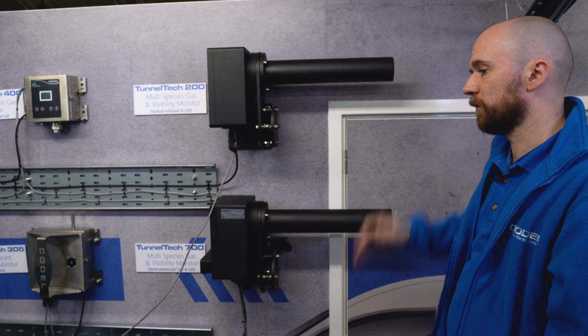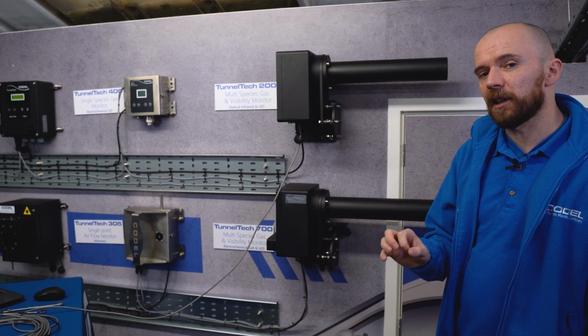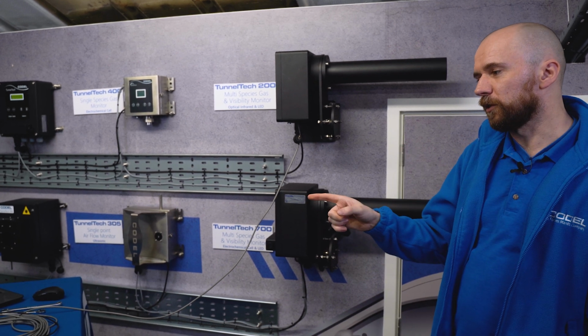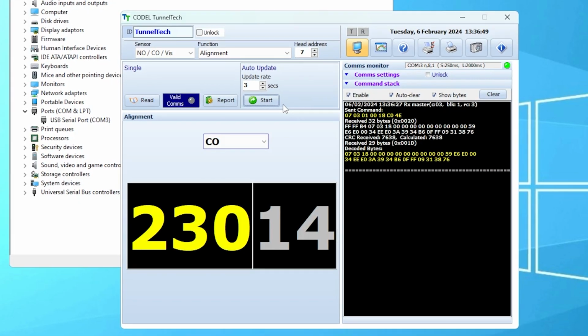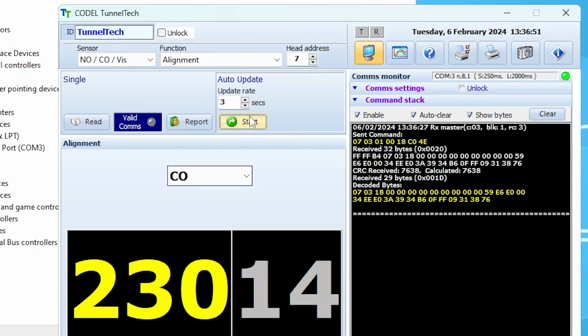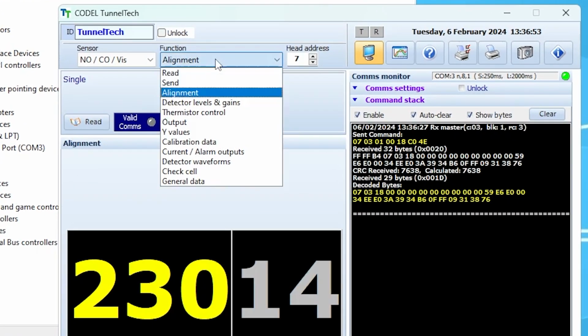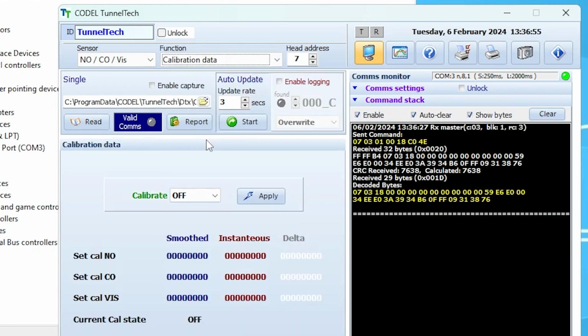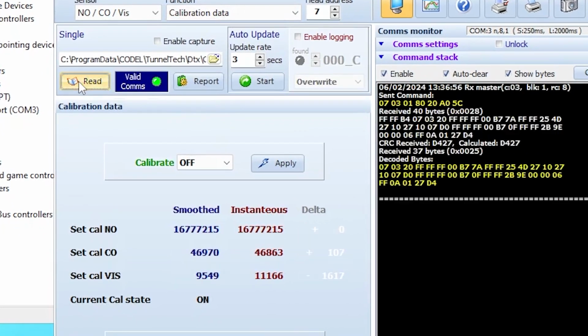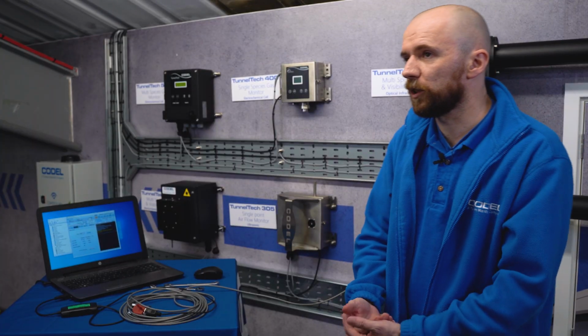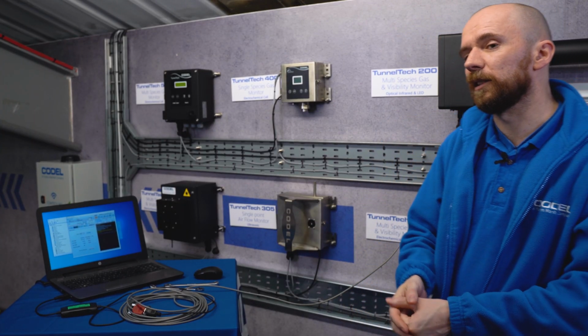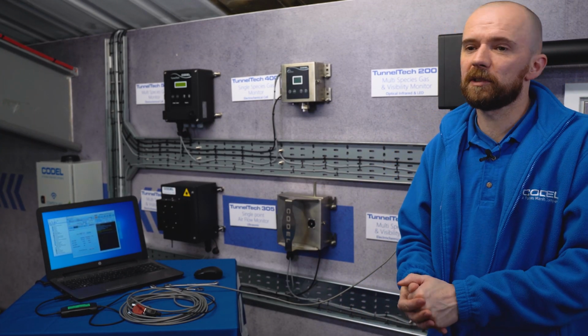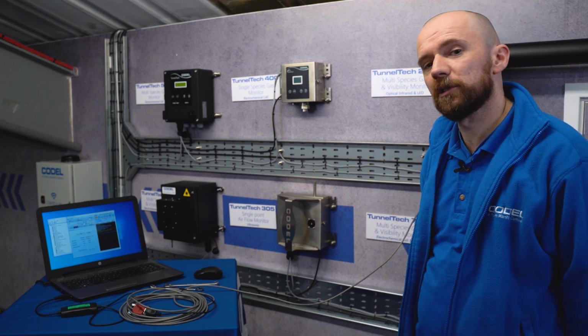We can double check that it's in calibration by going to the calibration function on the software. So if we just stop the auto update, and then from the function menu select calibration data, click read to do a single read, and you can see the current cal state down here is on. This calibration takes about 20 minutes and will automatically complete and go into measurement once we're finished.